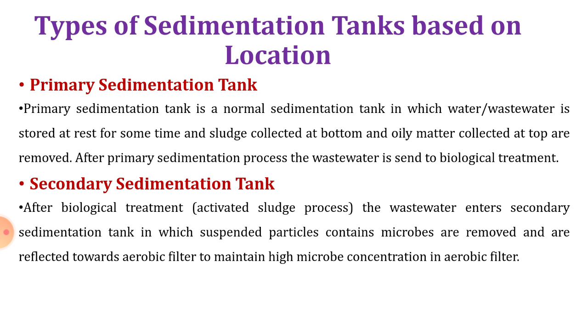Now, based on the location, the sedimentation tank is classified as a primary and secondary sedimentation tank. If the sedimentation tank is provided in the primary treatment, it is called a primary sedimentation tank. And if it is provided in the secondary treatment, then it is called a secondary sedimentation tank. Primary sedimentation tank is a normal sedimentation tank in which wastewater is stored at rest for some time. Sludge collected at the bottom and oily matter collected at the top are removed. After the primary sedimentation process, the wastewater is sent to biological treatment. So here in the primary sedimentation tank, only the suspended particles and oily matter are removed — a physical separation is carried out.